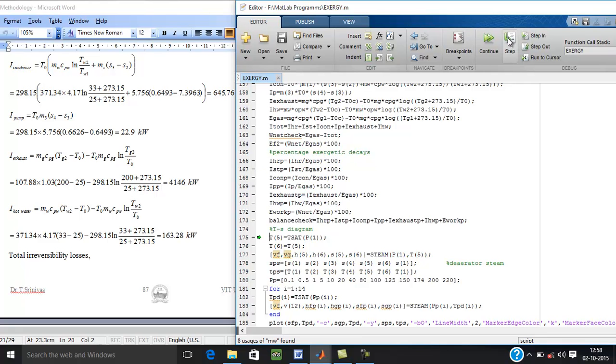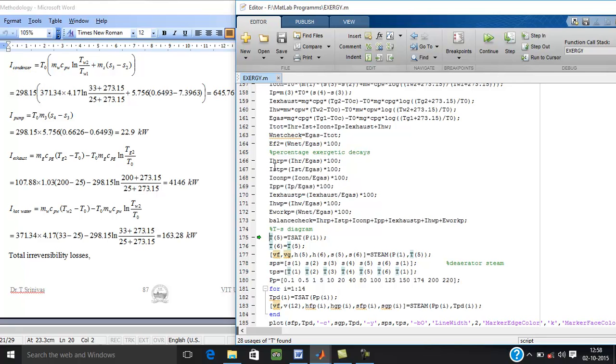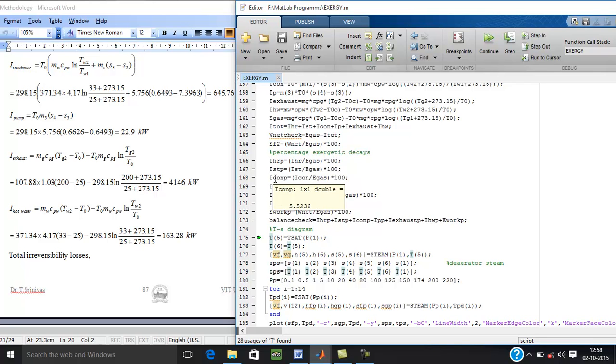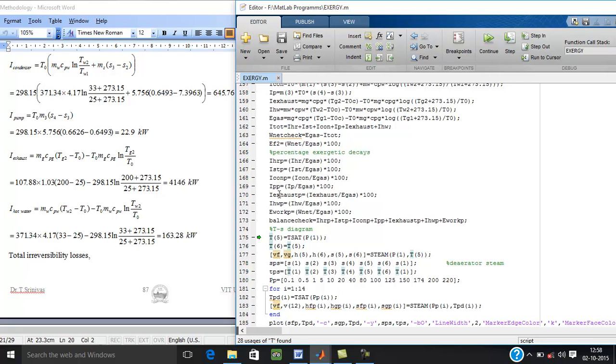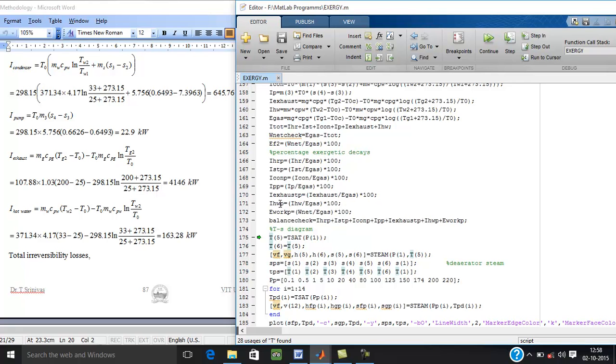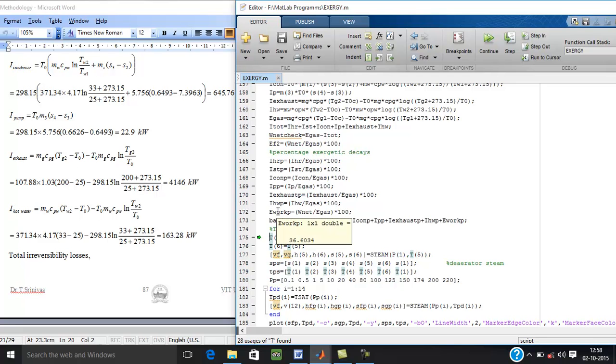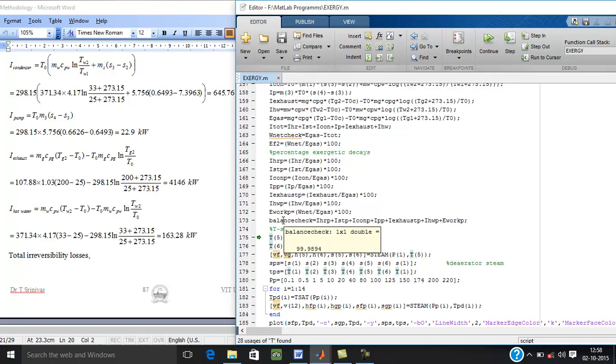Now see, percentage in HRSG is 14.73, steam turbine 6.07%, condenser is 5.52%, pump 0.19%, exhaust 35.46%, hot water 1.39% and exergy associated in the work is 36.6% which is equal to the second law efficiency. Now the exergy balance shows the sum of all irreversibilities in percent plus exergy associated with the work is 99.98%.